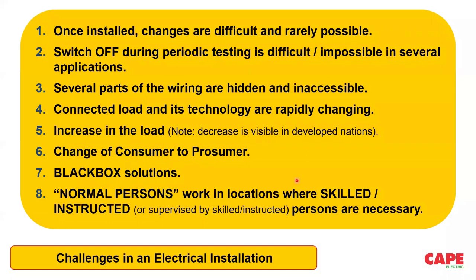Very, very, very dangerous. Now, the next point is that normal persons work in locations where skilled or instructed people are required, or where they should be supervised by skilled or instructed people. These are actually missing. A person who doesn't know much about the subject is working on or sometimes handling an electrical apparatus. This also creates a hazardous situation. For example, opening up a panel board which contains live parts, and without proper PPE, somebody putting a screwdriver into it and ending up in trouble. So these are also creating some of the issues. I have put only 8 points, but if we keep adding points, you can probably find 100 reasons why we violate electrical safety.